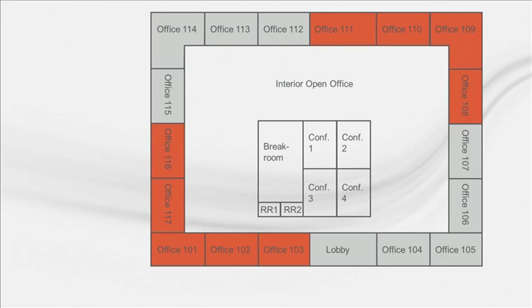with only morning warm-up. Like the example from a few minutes ago, you might run into trouble with respect to ASHRAE Standard 15 requirements if refrigerant piping crisscrosses the building. If the zoning makes sense, we can now use the software's output reports to select equipment using the VRF manufacturer's selection software. We could also continue with an energy analysis.